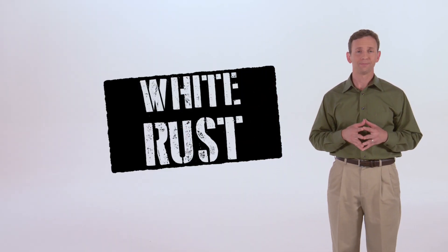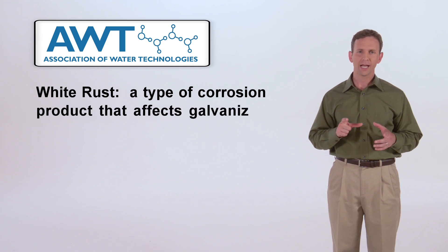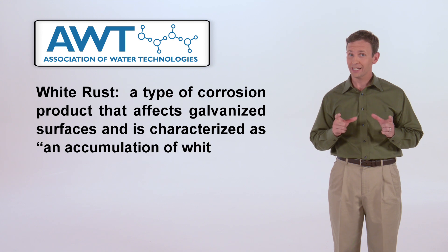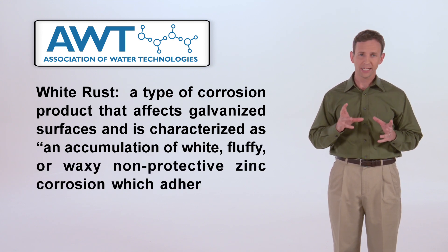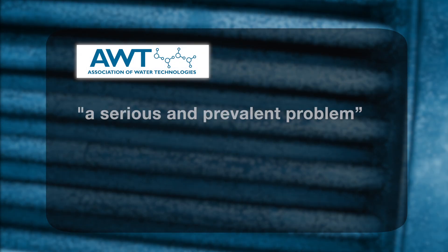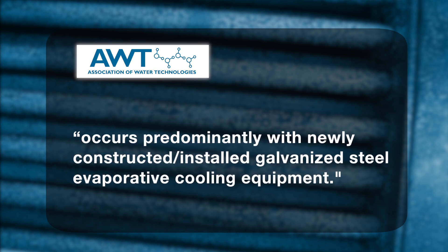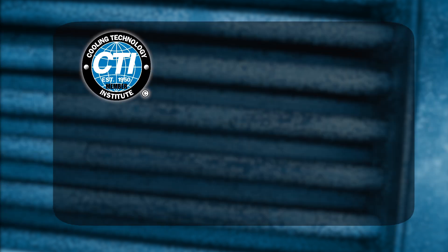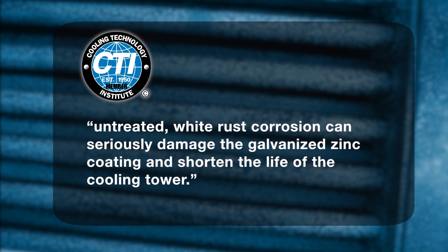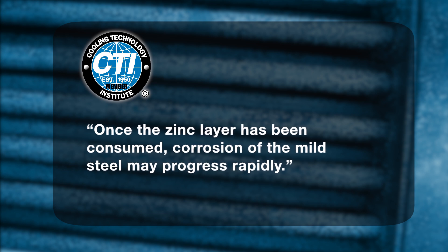And there we have it — white rust. The Association of Water Technologies defined white rust as a type of corrosion product that affects galvanized surfaces, characterized as an accumulation of white, fluffy, or waxy non-protective zinc corrosion, which adheres to the surface of galvanized steel. More importantly, a survey of AWT members identified white rust corrosion as a serious and prevalent problem, which occurs predominantly with newly constructed, installed galvanized steel evaporative cooling equipment. The Cooling Technology Institute stated in their 1994 publication that untreated, white rust corrosion can seriously damage the galvanized zinc coating and shorten the life of the cooling tower. Once the zinc layer has been consumed, corrosion of the mild steel may progress rapidly.